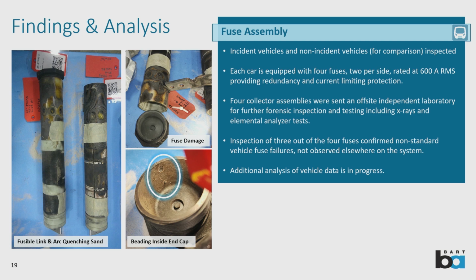The tests were extensive, including an elemental analyzer test on an area that looked like brass, which was confirmed to be brass. Those pins are actually zinc or zinc-plated, so it was interesting that brass was found there, since forming brass from zinc requires copper and extremely high temperature. It's yet to be confirmed, but the hypothesis is that there was high energy arcing in that area.